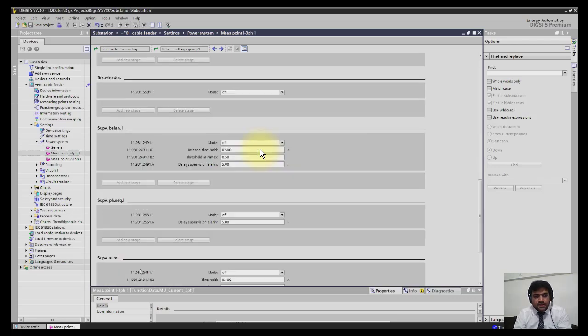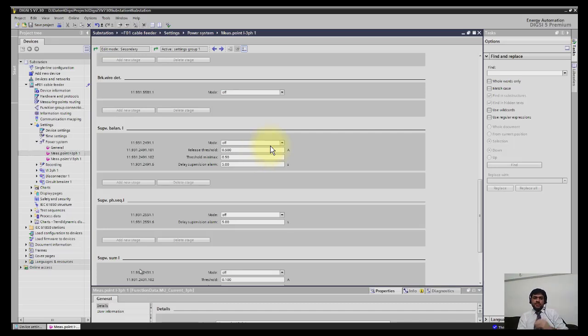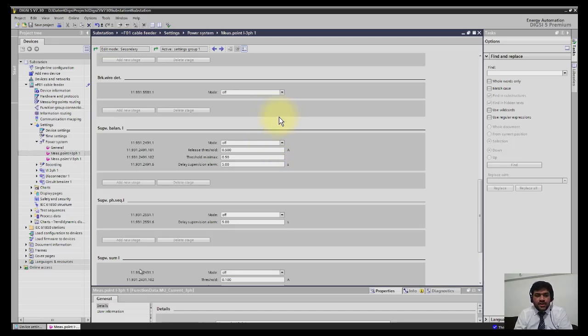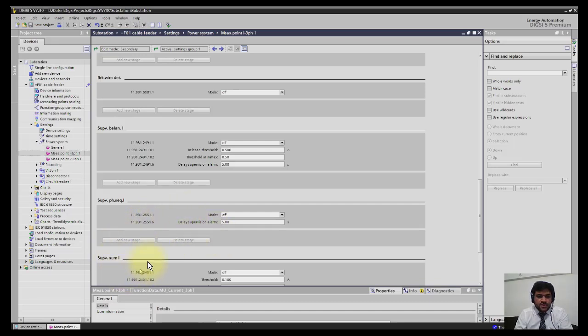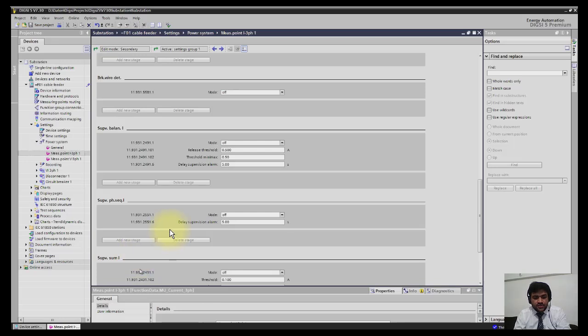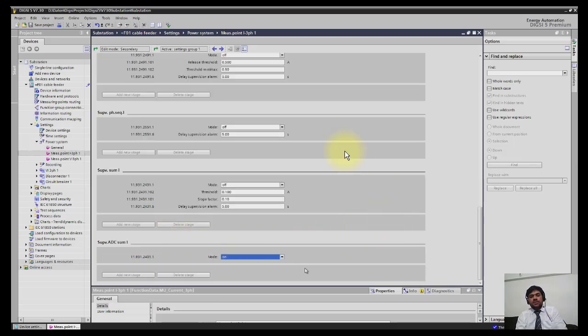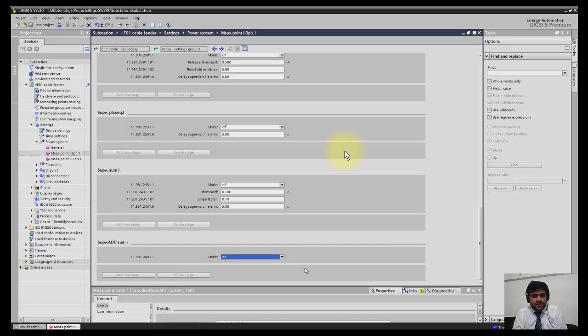You also have here CT supervision. For each module, you can find the supervision settings. We have supervision of unbalanced current, phase supervision of phase sequence—it will check the phase and if the sequence is wrong, certain functions can be configured.